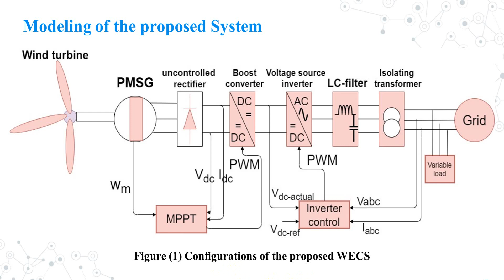Modeling of the proposed system. The proposed wind energy conversion system used in this research consists of a wind turbine directly connected with a permanent magnet synchronous generator, a three-phase uncontrolled rectifier, a DC to DC boost converter, control on the generator side which is called MPPT control, and a three-phase voltage source inverter connected to the main grid by an LC filter to reduce ripple in voltage and current, and a three-phase isolating transformer for the purpose of protection and isolation, as well as a control system on the grid side. The variable loads are connected at the point of common coupling.